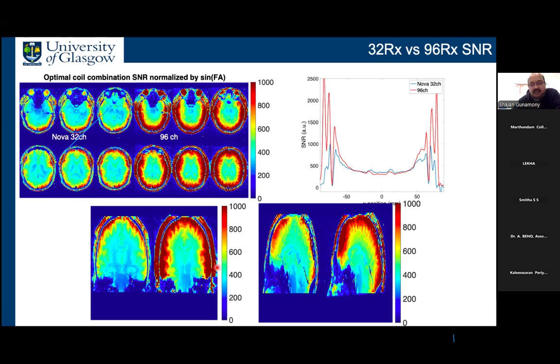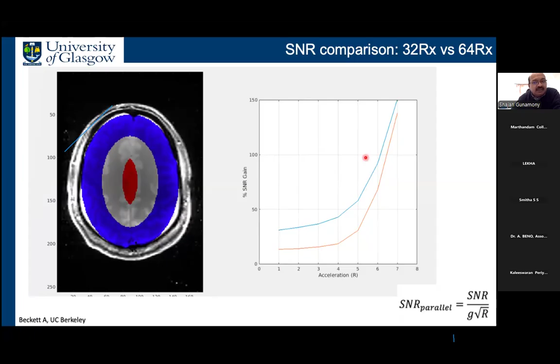So again, this is a comparison between a 32-channel and a 64-channel coil. And as I said already, when we increase the number of channels, then you gain in parallel imaging performance, and the G factor for a higher channel coil is always lower. So you pay less penalty. And this is what you see here. There are two regions of interest, one in the center of the brain, which is marked in red, and the periphery is marked in blue. You see without acceleration, the two coils, 32 and 64, are quite comparable, but as you increase the acceleration factor, you get so much higher SNR with the 64-channel coil.